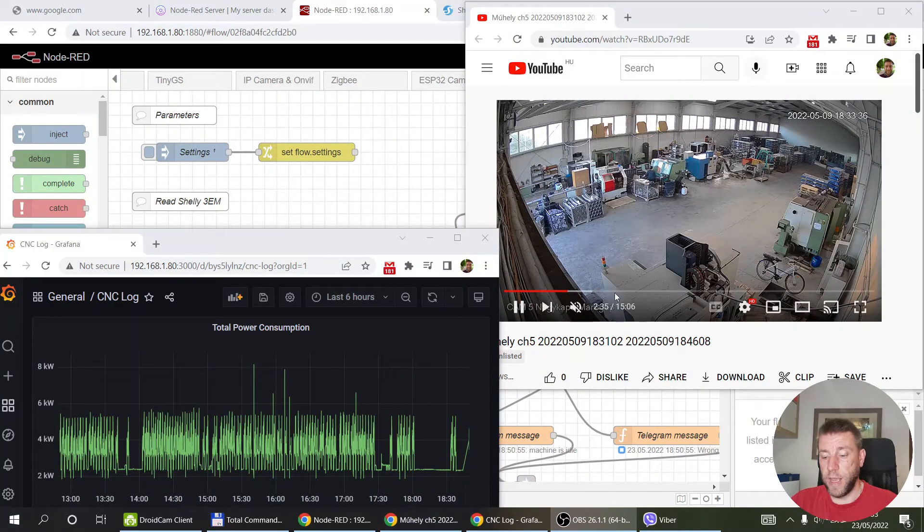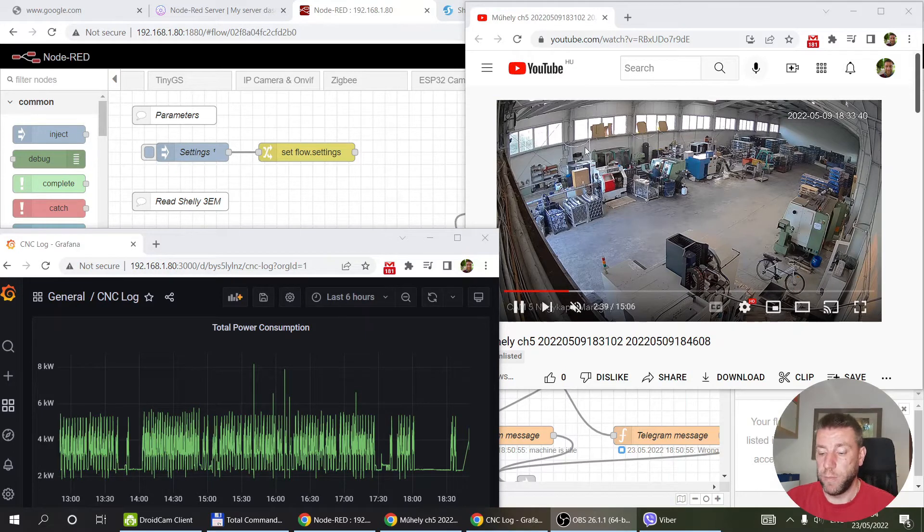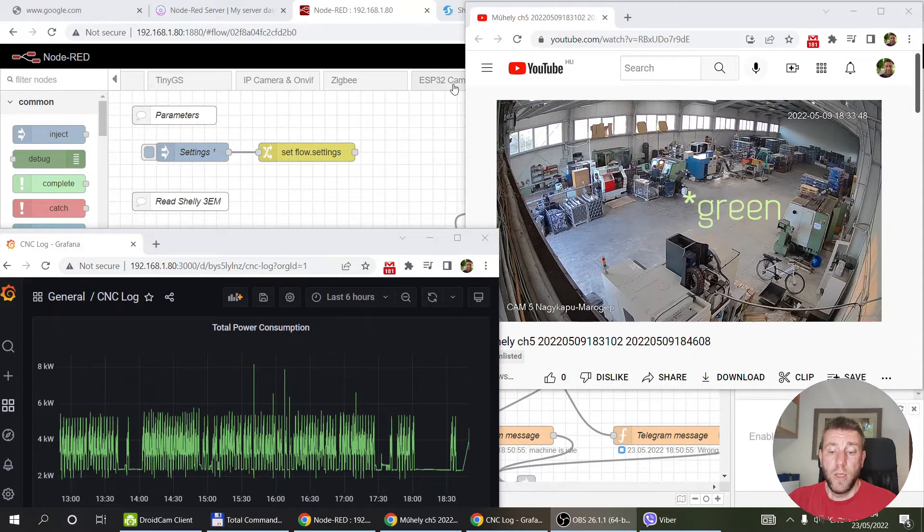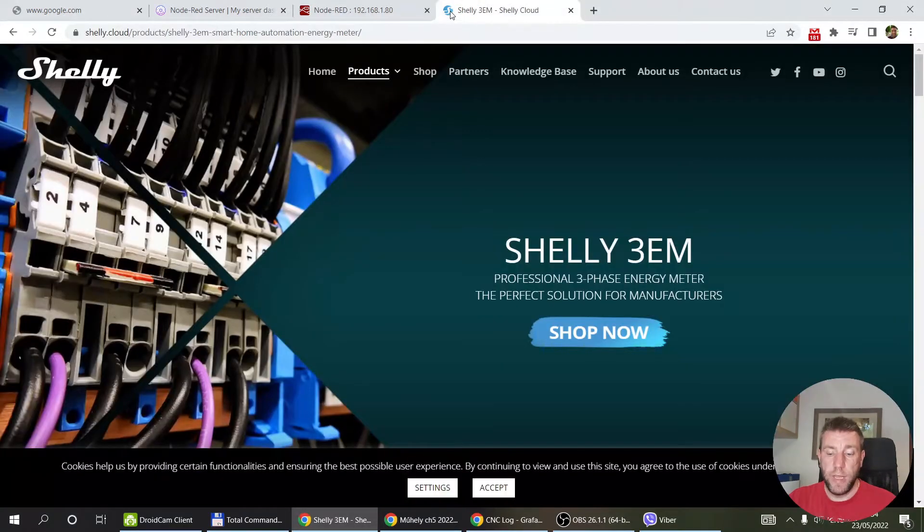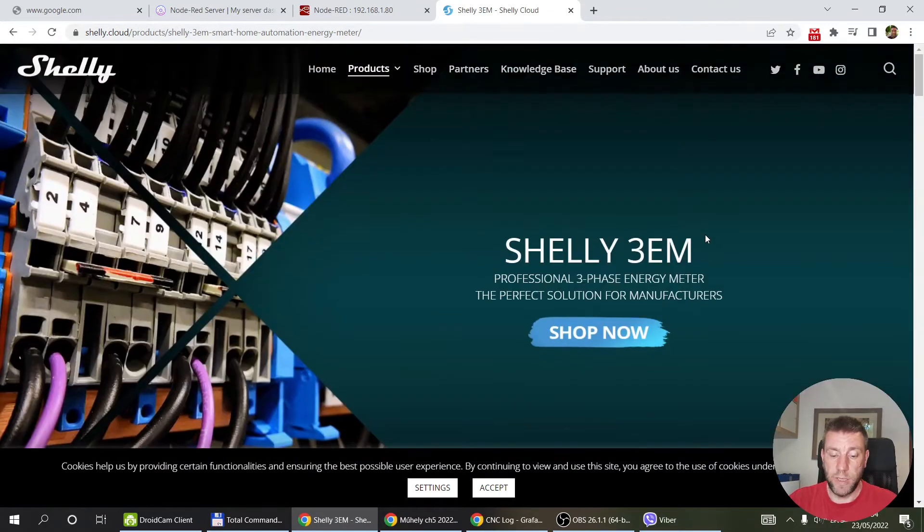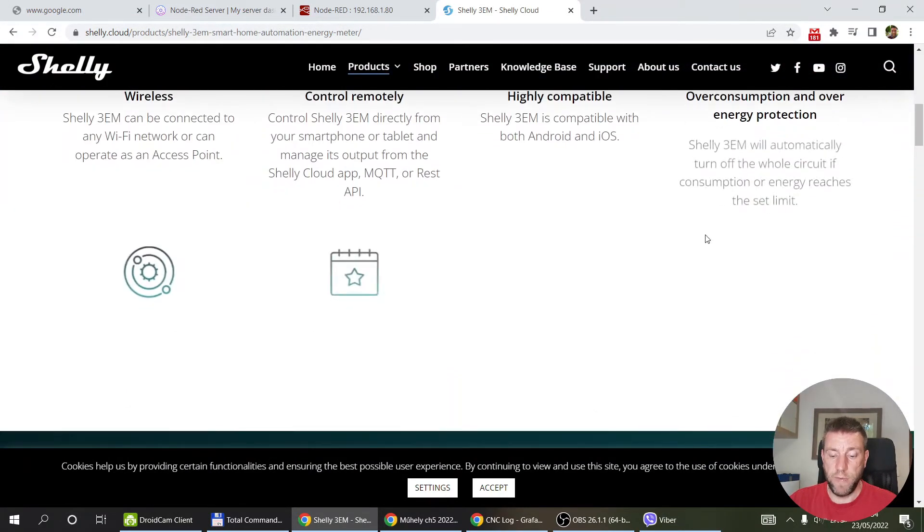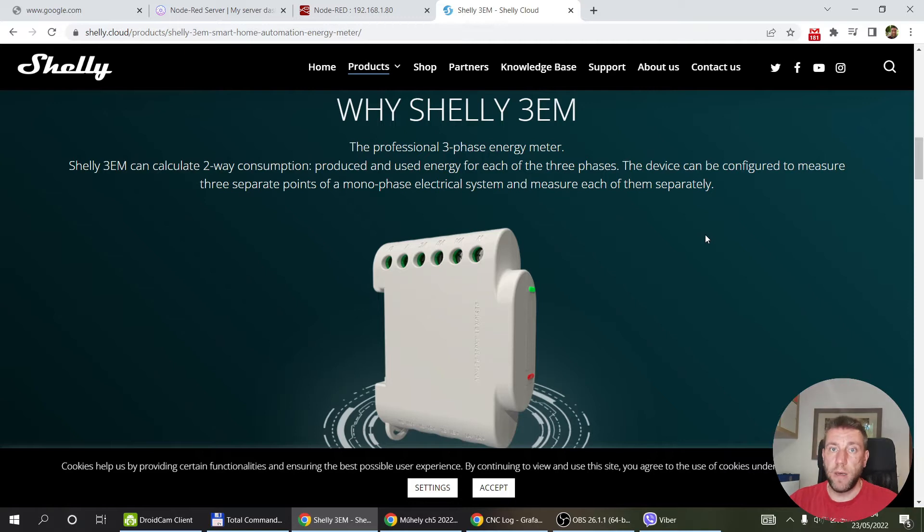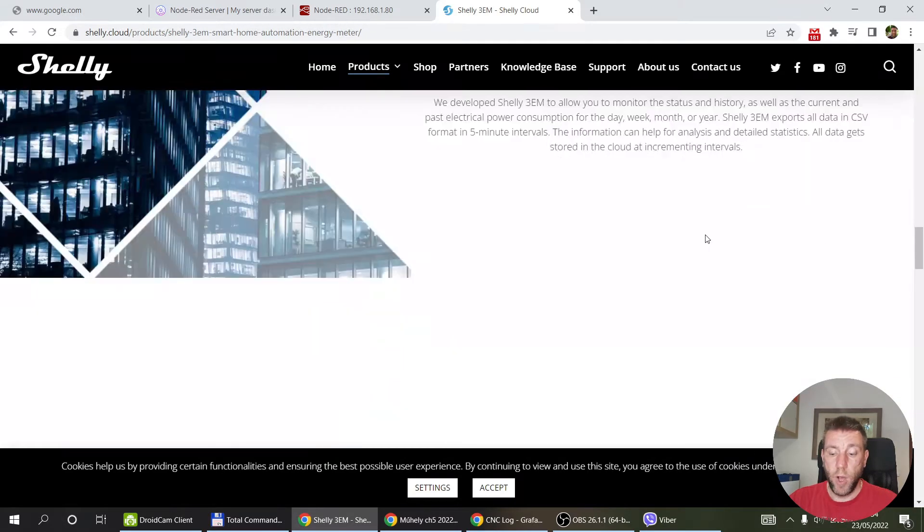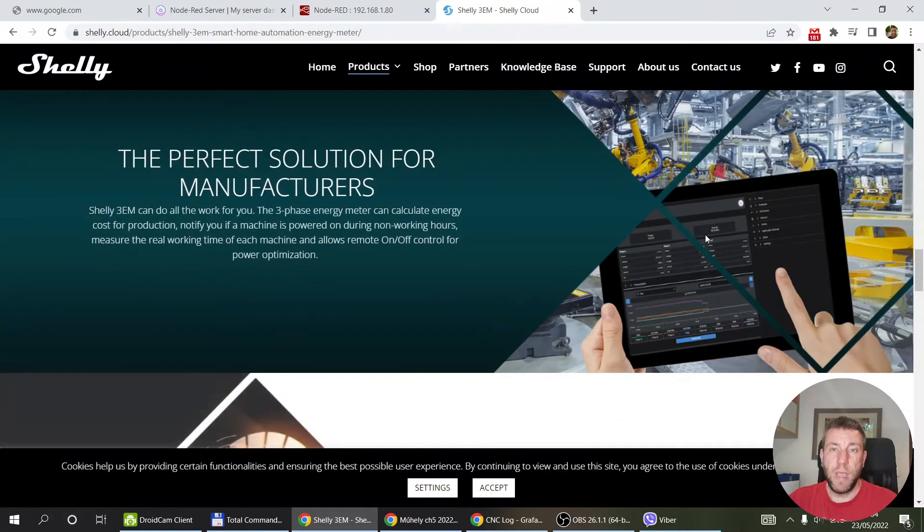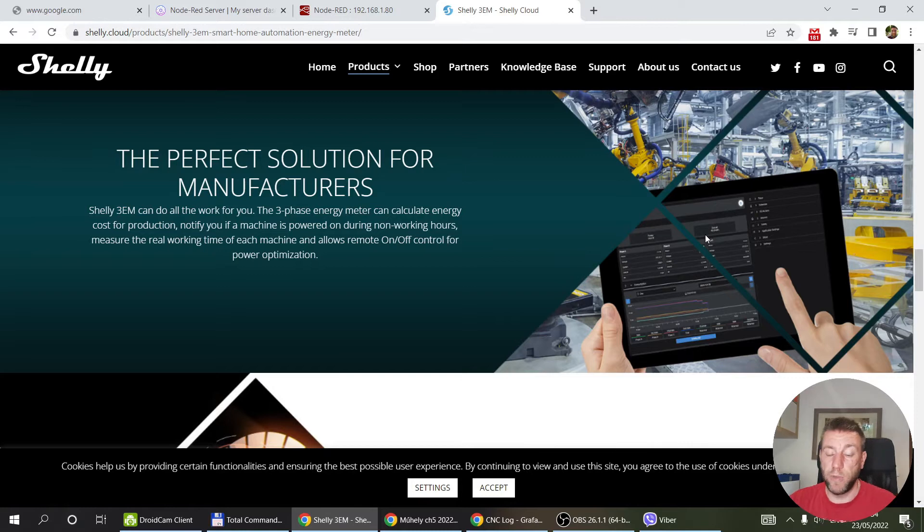You can see here a recording from the machine shop, and this is the blue CNC machine that we will be monitoring. What I asked my friend to do is install a Shelly 3EM, which is a three-phase current monitoring device with current clamps that measures voltage, amps, and calculates the watts on all three phases. I thought maybe by looking at the overall consumption or single phase consumption, I would be able to figure something out.